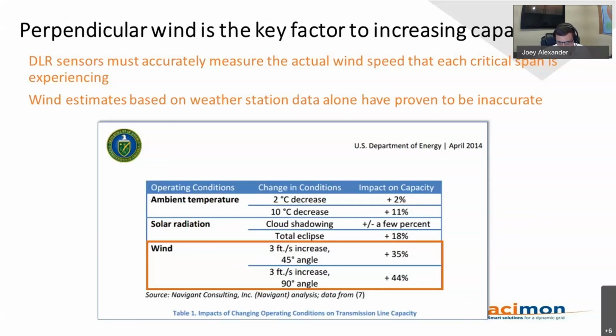The scary thing about wind is that it's extremely dynamic. Unlike ambient temperature, which is fairly homogeneous and predictable, wind changes readily depending on elevation, so the wind the conductor experiences can be quite different from the wind at ground level. If you take wind data from weather data systems, that data is probably coming from an airport weather station, and they're interpolating what the wind is in an area where it probably doesn't know how to do that. So it's really important that wind is accurately measured as it impacts the line, and that there's an accurate assessment of the perpendicular wind crossing the line, because that's what gives the highest impact.